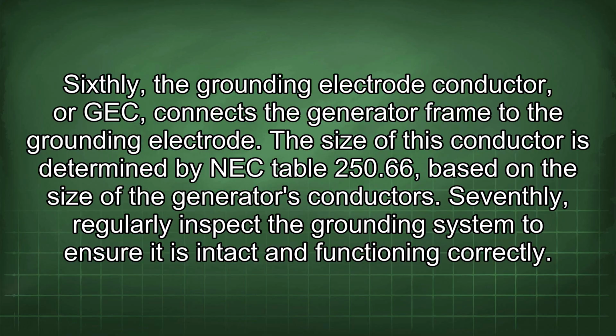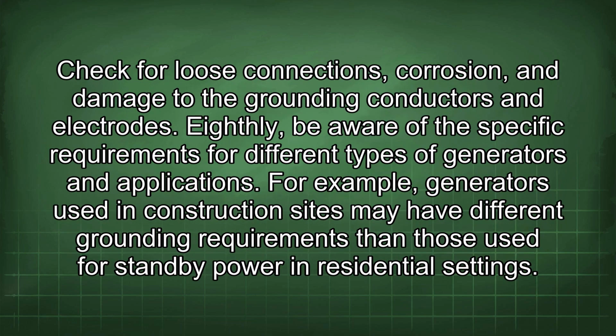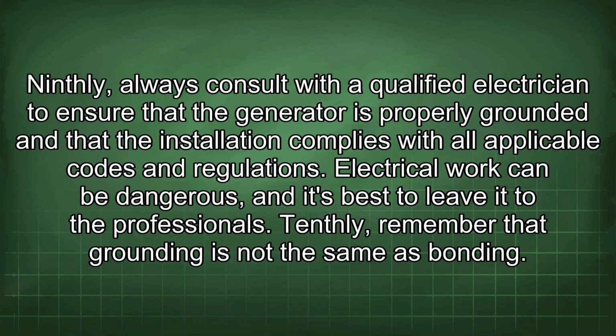Seventhly, regularly inspect the grounding system to ensure it is intact and functioning correctly. Check for loose connections, corrosion, and damage to the grounding conductors and electrodes. Eighthly, be aware of the specific requirements for different types of generators and applications. For example, generators used in construction sites may have different grounding requirements than those used for standby power in residential settings. Ninthly, always consult with a qualified electrician to ensure that the generator is properly grounded and that the installation complies with all applicable codes and regulations.